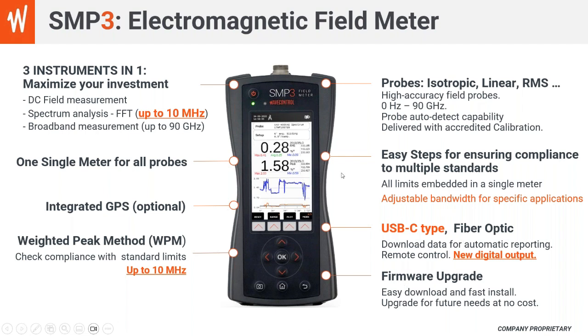Then also it allows you to connect the device via USB-C cable or fiber optic cable to do live measurements. It also allows you to do weighted peak method going up to 10 megahertz to have a direct comparison with the standard limit, to have a direct weighted percentage with respect to the limit. You also have GPS integrated with the device. So for example, you do a measurement, you can have the GPS information for all the measurement samples which are taken.